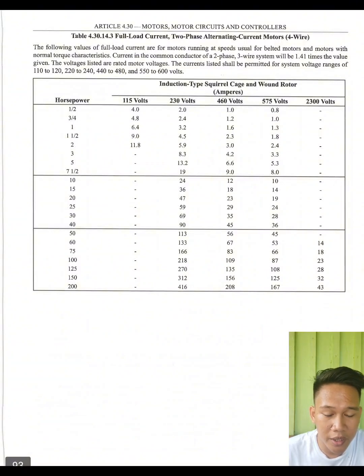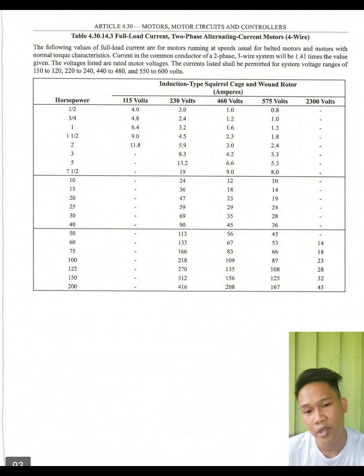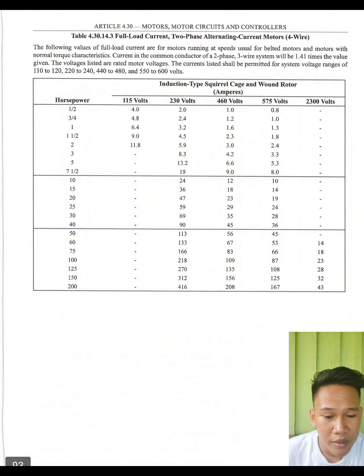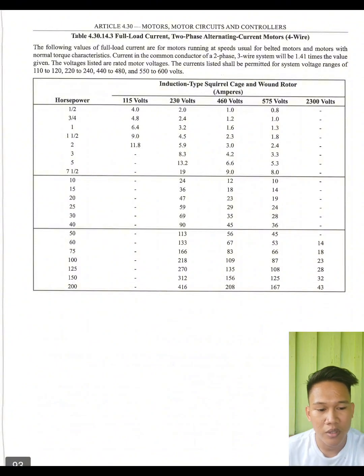So, makita daw sa table rin na itong presing niya po sa itong mga last na kuan. Horsepower na 1/2, 3/4, sa value sa horsepower. Then, sa induction type, squirrel cage and wound rotor, amperes. So, yung 115 volts, 230 volts, 460 volts, 575 volts, and 2,300 volts. Example, kanyang 1/2 horsepower. Sa 115 volts na 4.0, 230 volts 2.0, 460 volts 1.0, 575 volts 0.8, sa 2,300 volts wala. And so on na siya.